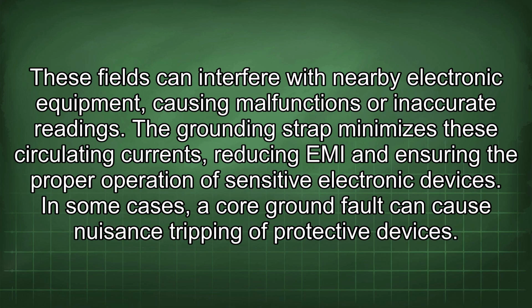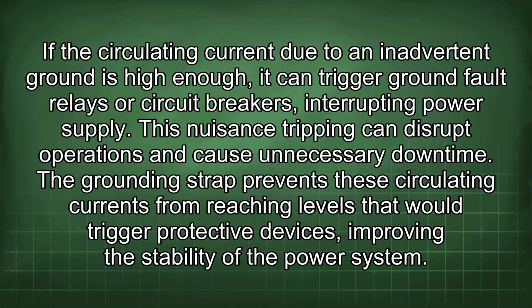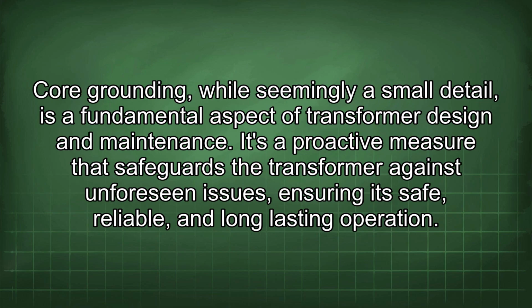In some cases, a core ground fault can cause nuisance tripping of protective devices. If the circulating current due to an inadvertent ground is high enough, it can trigger ground fault relays or circuit breakers, interrupting power supply. This nuisance tripping can disrupt operations and cause unnecessary downtime. The grounding strap prevents these circulating currents from reaching levels that would trigger protective devices, improving the stability of the power system. Core grounding, while seemingly a small detail, is a fundamental aspect of transformer design and maintenance.